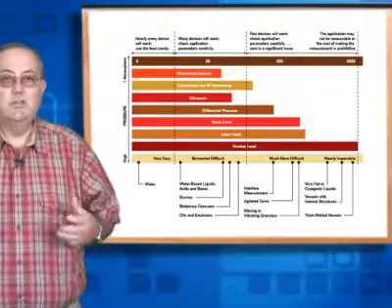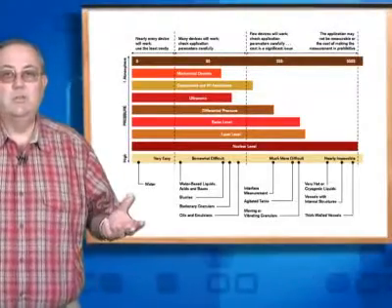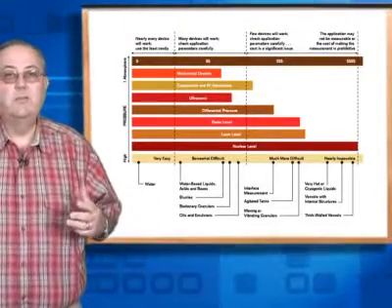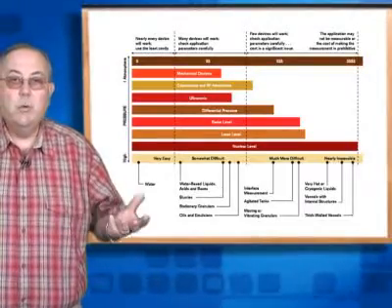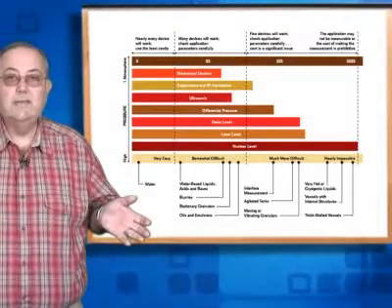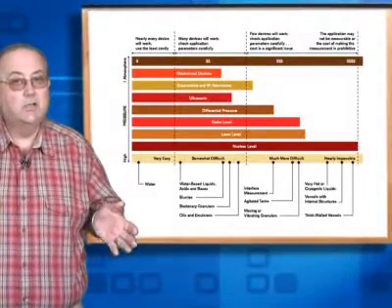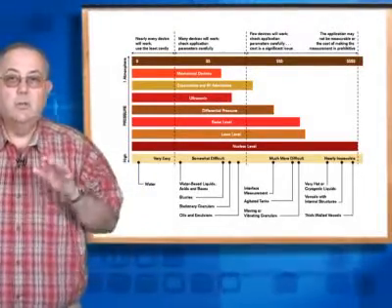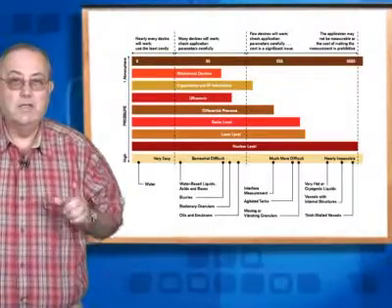Most of us get so practiced with instrumentation design that we seem to start with the last ISA20 instrument specification form that we worked with and just plug the new numbers in. But the S20 forms were not designed to be application selection guides. You start with the sensor or transmitter, and that's backwards.